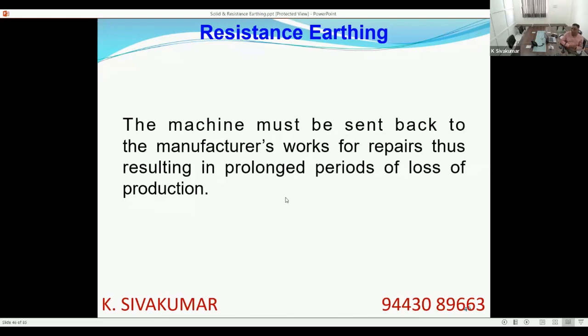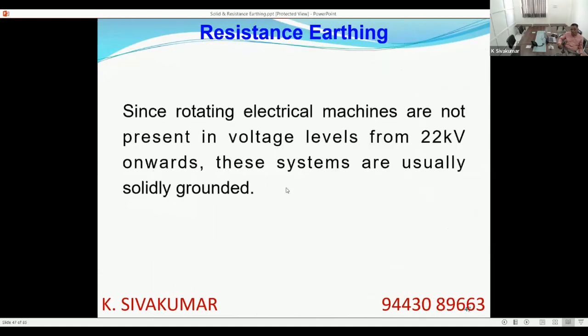So core damage always takes prolonged periods of downtime in the factory and loss of production. So one must try to avoid this situation. One must try to avoid core damages. How to do it? It can be done by resistance earthing only. Then taking forward, rotating electrical machines are not present at 22 kV onwards. Less than 22 kV we have seen generators; 24 kV generators are there, and motors up to 11 kV are there. Maybe I have not come across any 22 kV motor, whereas 22 kV generators I have seen. 3.3, 6.6 and 11 kV motors are available. So rotating machines are present in the network right up to 22 kV.